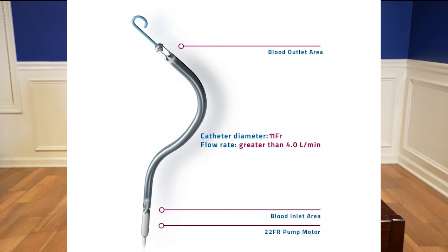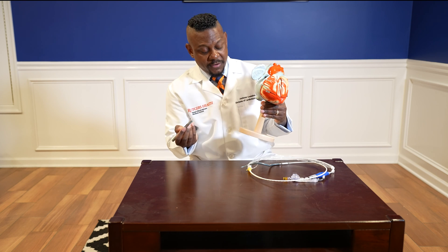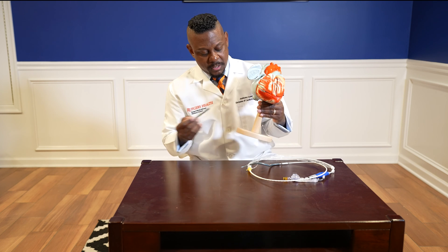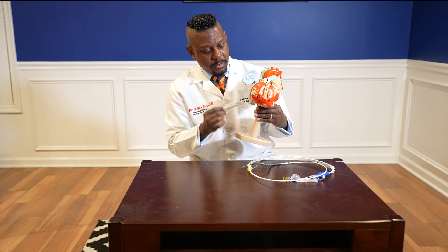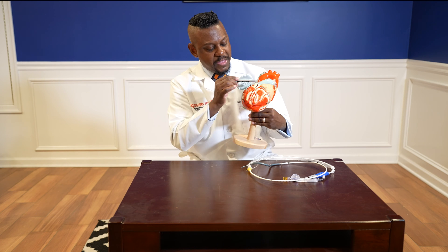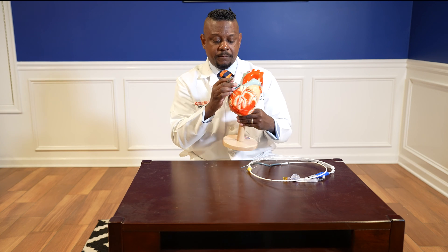With our model of the heart here, the inferior vena cava is right here, so the input area goes there, and the output area goes into the pulmonary artery. Blood is pulled out of the inferior vena cava and pushed into the pulmonary artery, allowing the right ventricle and right heart to rest.